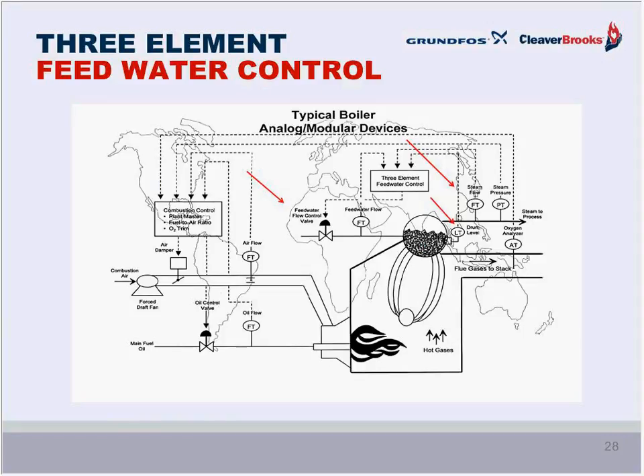Now, there's one last thing that I wanted to briefly review with you before turning the reins over to Jim, and that is the three-element feed water control. This is normally applied to critical process loads and industrial water tube boilers, where very precise level control is very important in avoiding wet steam and boiler outages. The concept involves three interrelated elements: water level, steam flow, and feed water flow.